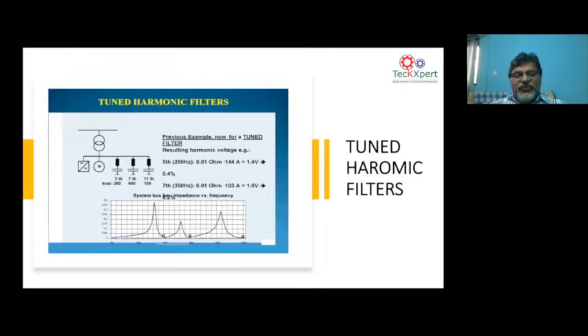The other way of filtering the harmonics is using tuned passive filters. As you can see here, in a network, like in an office situation or in a factory, you have lighting loads and variable frequency loads, and then you have a lot of third, fifth and seventh harmonics. In this particular example, we are showing you have fifth and seventh. You can install a passive filter to tune it away. So this is another way.